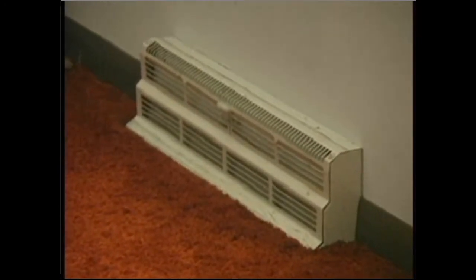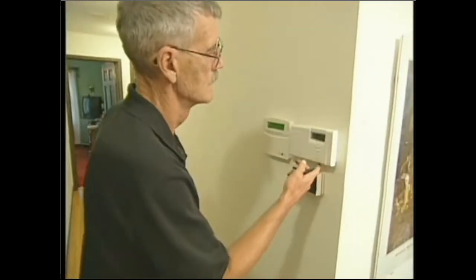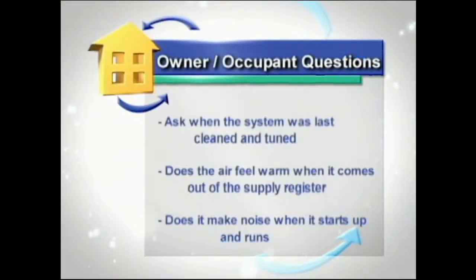And then I will check the thermostat. When I check the thermostat, I'm going to record the temperature that I have so I can return it back to the state that I found it so I don't get a phone call down the road. Sure. And then I will ask the homeowner a few questions like, when's the last time the unit has been cleaned and tuned? Does the air feel warm when it comes out? Does it bang? Does it pop? Does it make noise? Because you'll never know that furnace as well as that homeowner will.